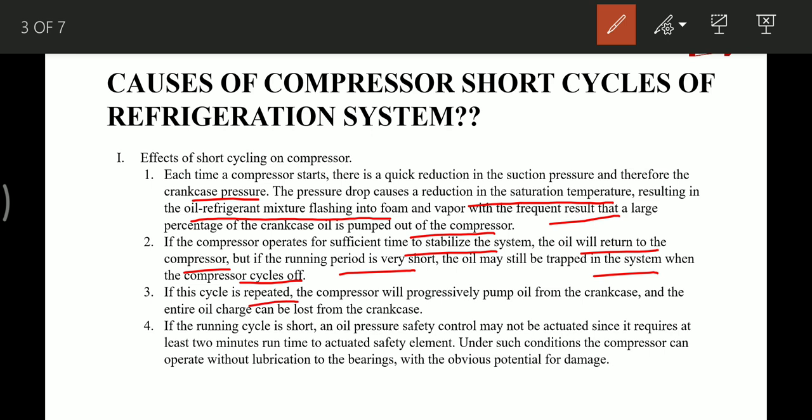If this cycle is repeated, the compressor will progressively pump oil from the crankcase and the entire oil charge will be lost from the crankcase. If the running cycle is short, the oil pressure safety control may not actuate since it requires at least two minutes run time to actuate this safety element.